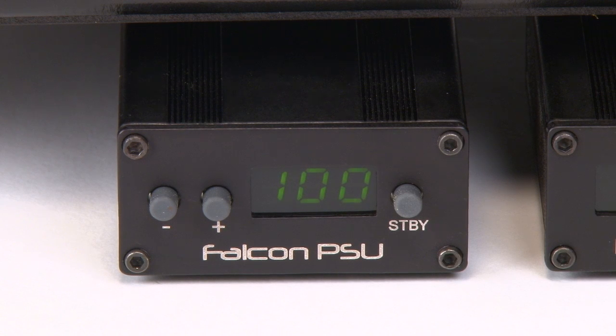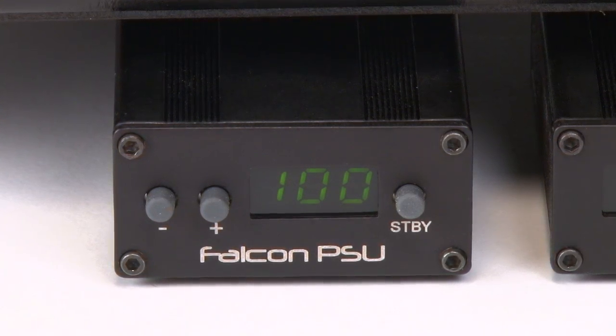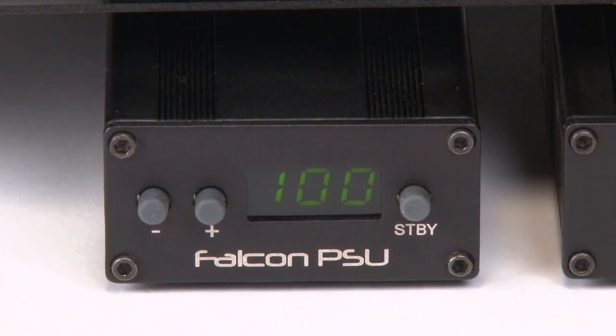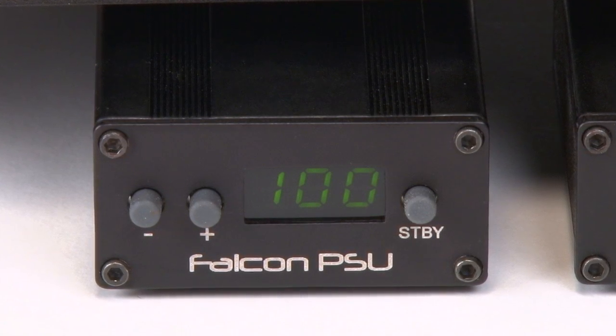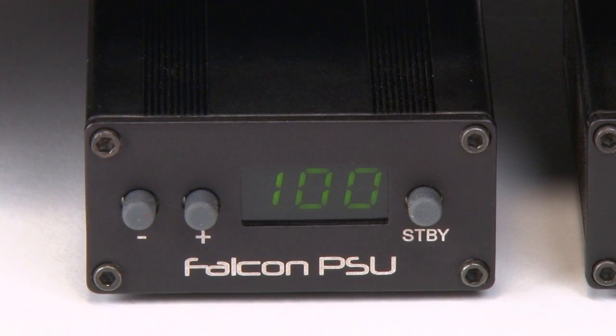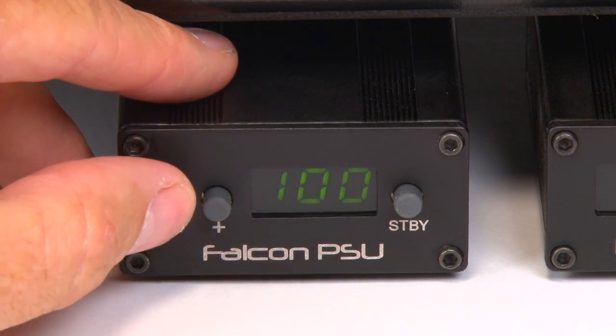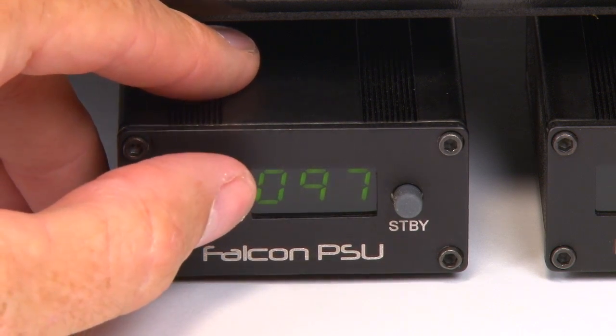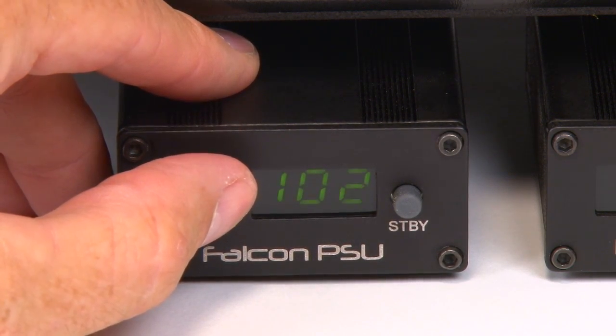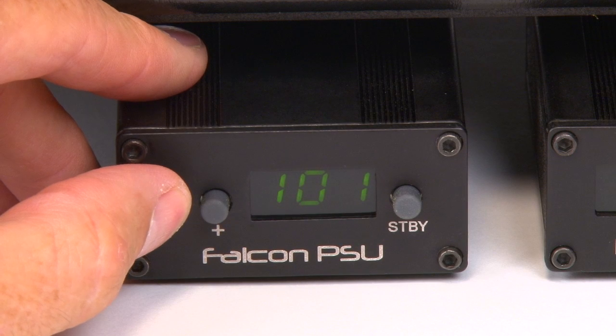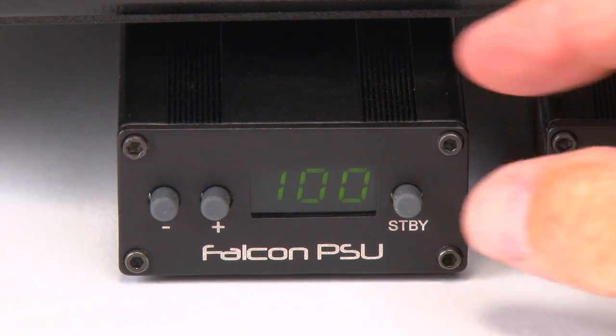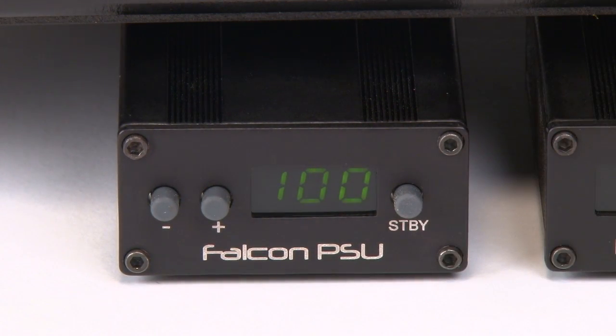The display is an approximation of the output voltage. For more accurate adjustment, connect a voltmeter to the output while making the adjustment. Change the output voltage using the plus and minus buttons for the lowest vibration while running at that speed. Each press of the button changes the output voltage approximately 1 volt. To select the other speed, press and release the standby button.